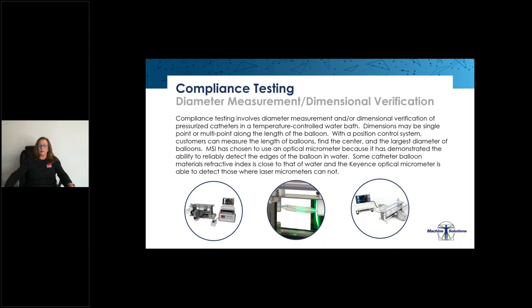MSI has chosen to use an optical micrometer because it has demonstrated the ability to detect the edges of the balloon in water. Some catheter balloon materials' refractive index is close to that of water, and the Keyence optical micrometer is able to detect those where we have found the laser micrometers cannot.